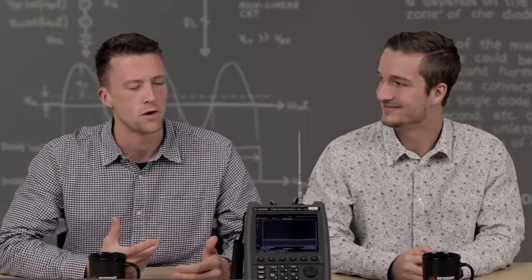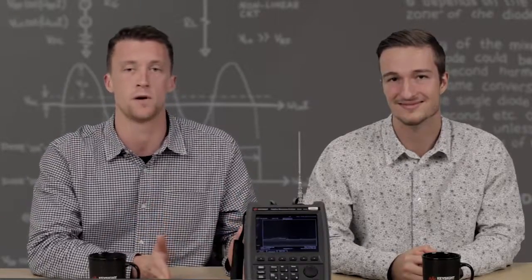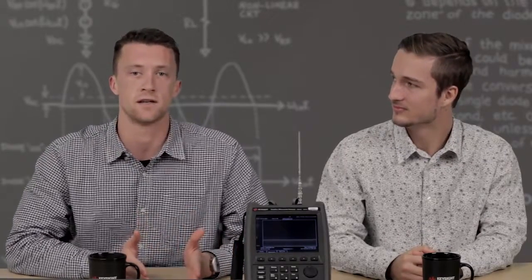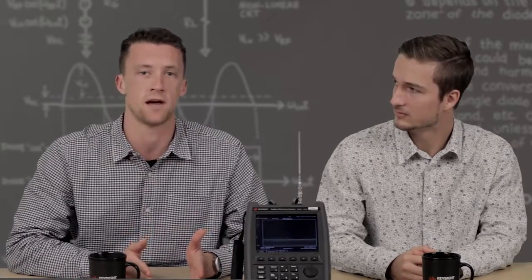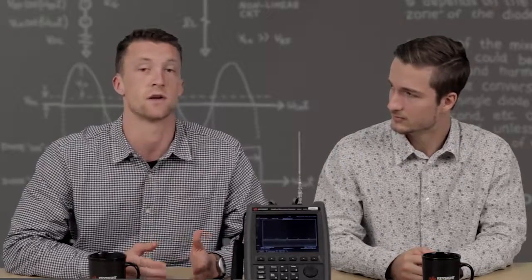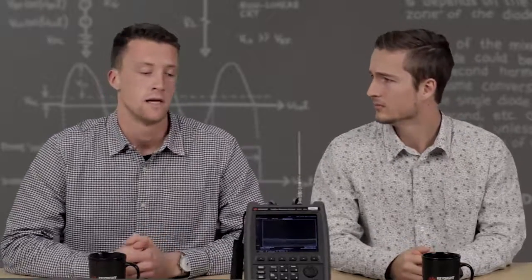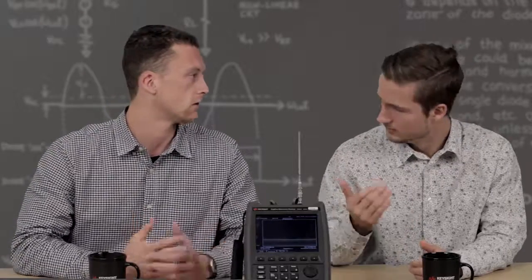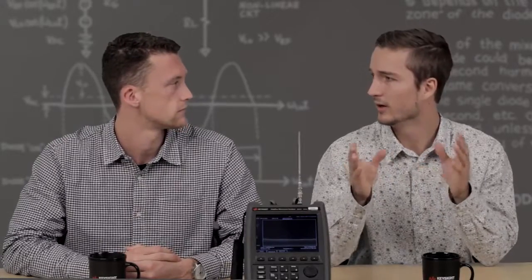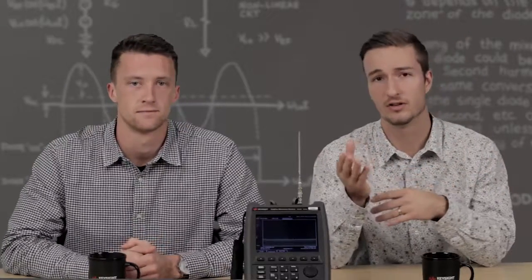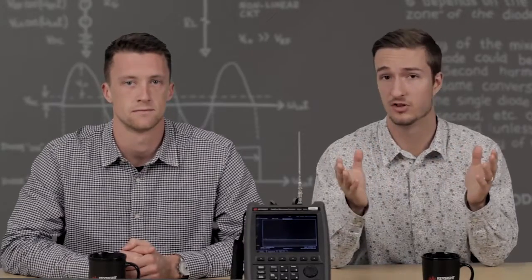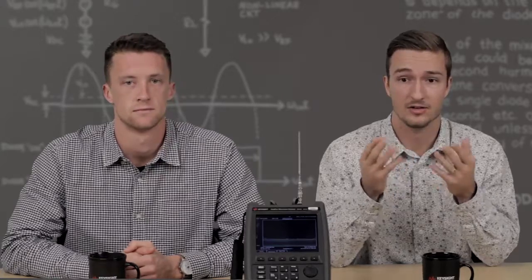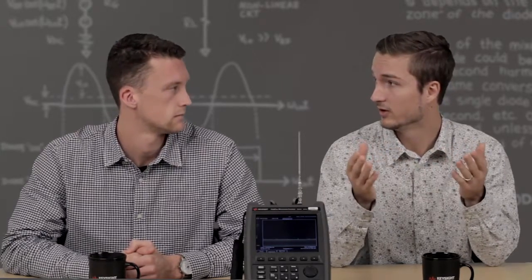In traditional SA mode, the FieldFox is taking measurements for a small period of time and measuring amplitude over time, and then a small period of time after that, converting that data through FFT math to a frequency spectrum and putting this on the display. As a result, the FieldFox actually has small periods of time where it's not acquiring any data at all. Yeah, and problems can occur where if you have a quick pulsing signal or a spectrum that's rapidly changing over time, you can actually miss your signals and not get a full view of the frequency content that you're trying to look for.